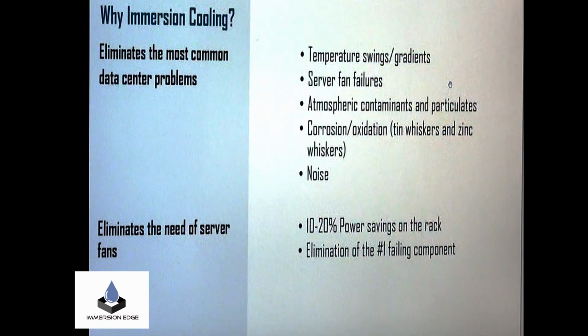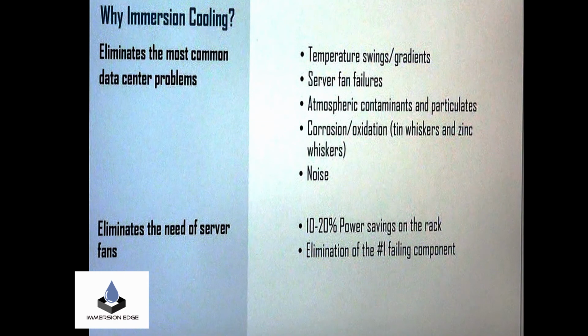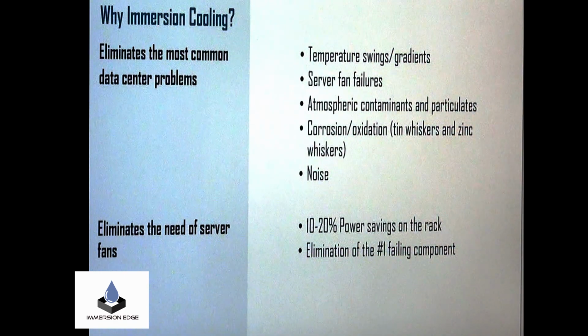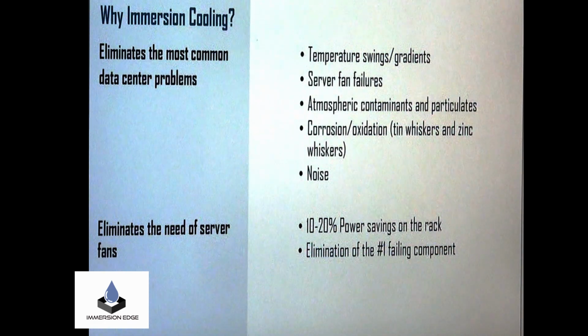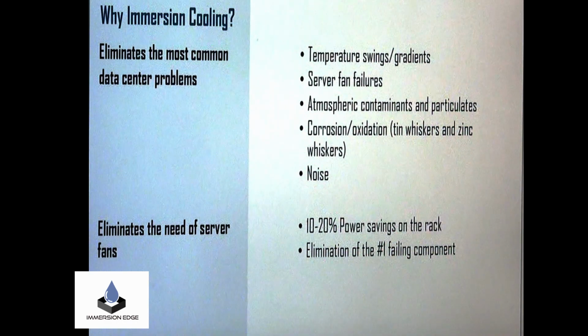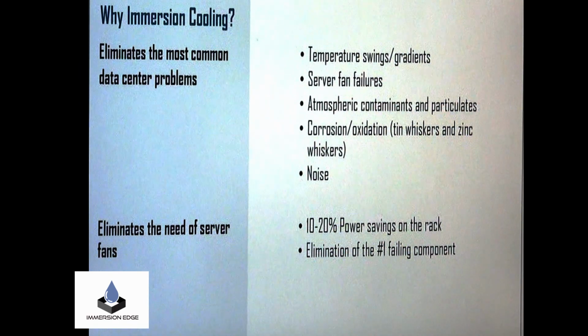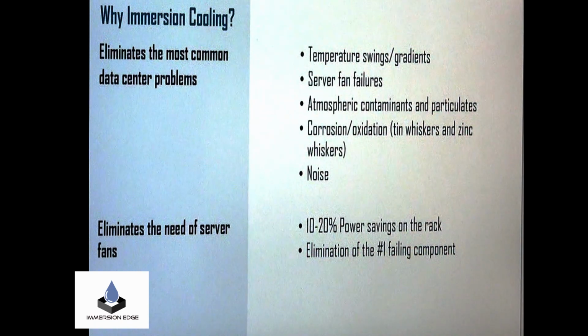It eliminates some of the most common data center problems: temperature swings, server fan failures, a lot of contaminants in the air, dust, corrosion, oxidation, and noise, which is also a really big factor considered a problem in a lot of data centers. It also completely eliminates the need for server fans. I heard a really interesting fact that the fans themselves are 10 to 20% of the energy for a server. So when you eliminate that, you're also eliminating the number one failing component, not to mention the energy required for the fans. So by removing the fans, you start chipping away at the energy right away. I'm going to the next slide.